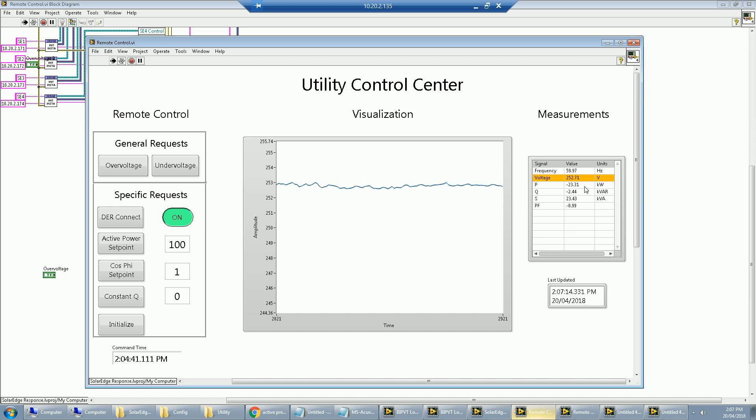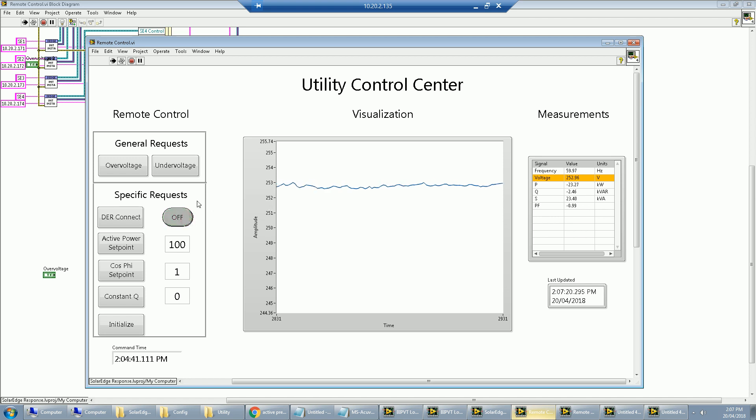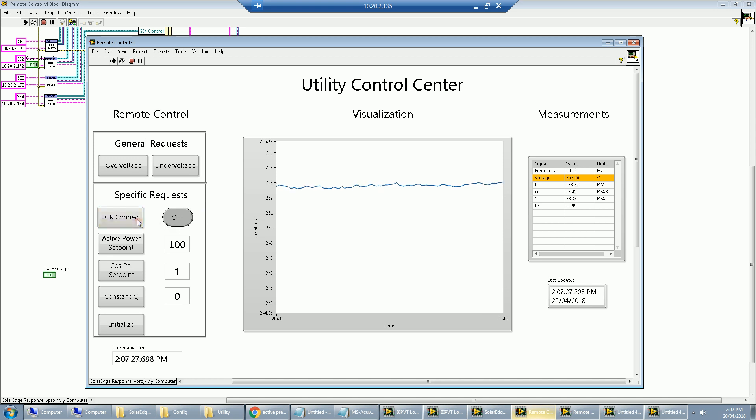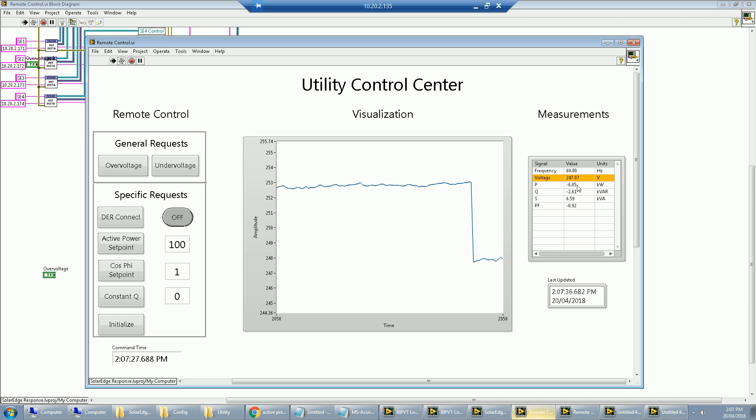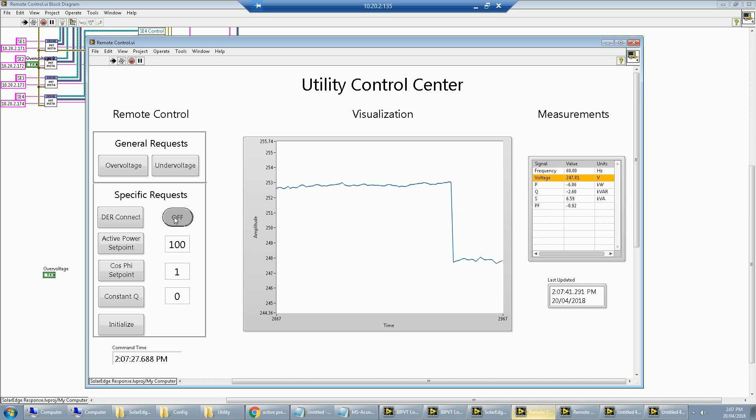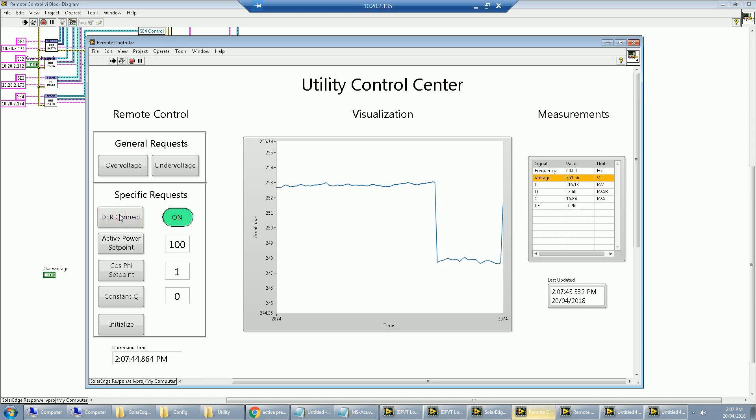To demo the software, what I can do is turn those smart inverters off. So about 20 kilowatts I can affect just by pressing this button. Immediately, we see the voltage drop, and that's primarily because the active power generation just reduced from 24 to 6. Just as instantaneously, I can bring it back up, and we go right back to where we started from.